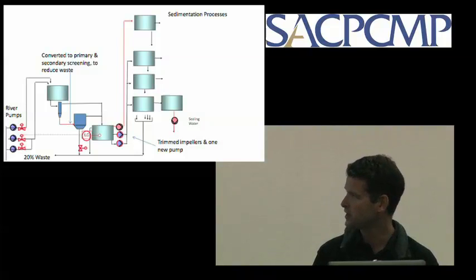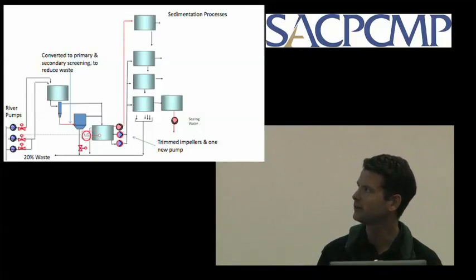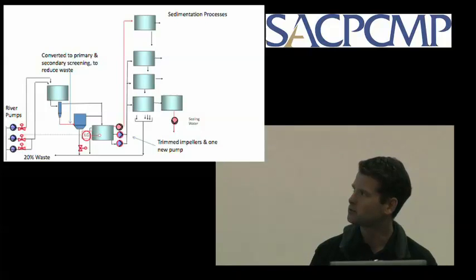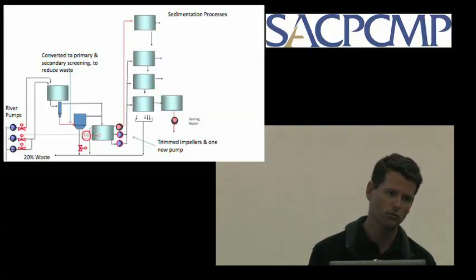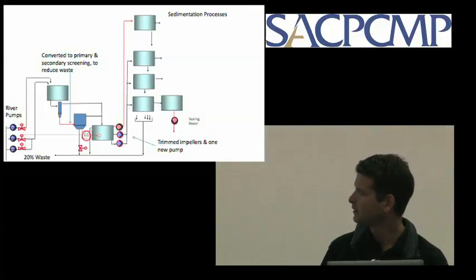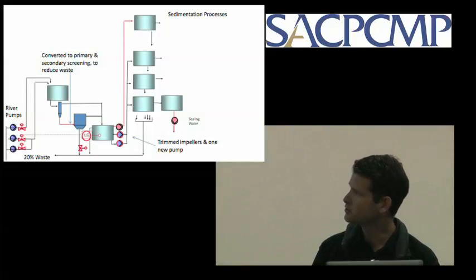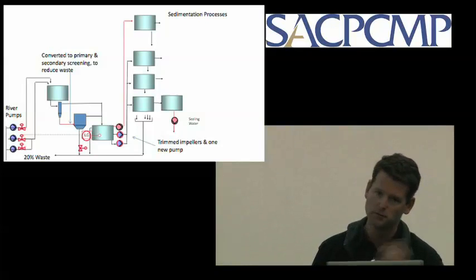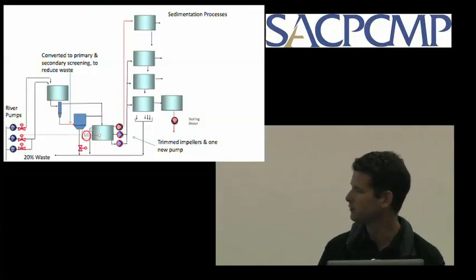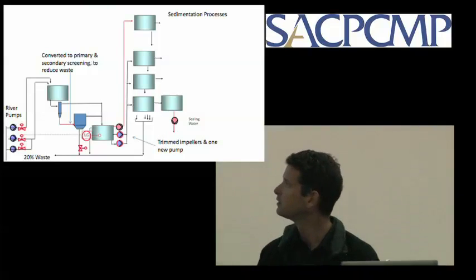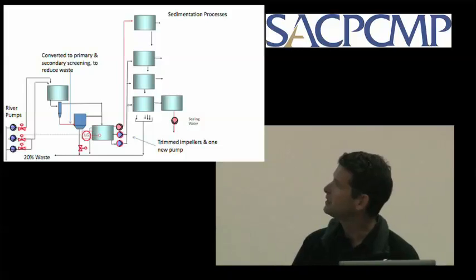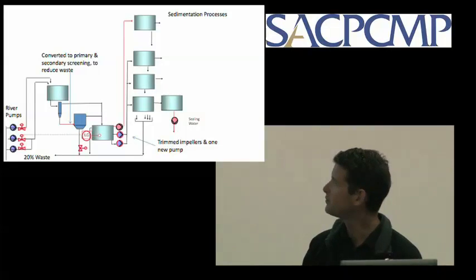So these valves also had an added function in addition to controlling that level, instead of just overflowing it like they were previously. When the pumps stop, those valves close and you don't drain all this water back into the river and lose more of a prime than you need to. And then if you start up, sometimes they literally open those valves to back flush it and speed up the priming process. So that's part of the P&ID where we've automated that and put the control valves in, and a flow switch to detect when the pumps are primed.